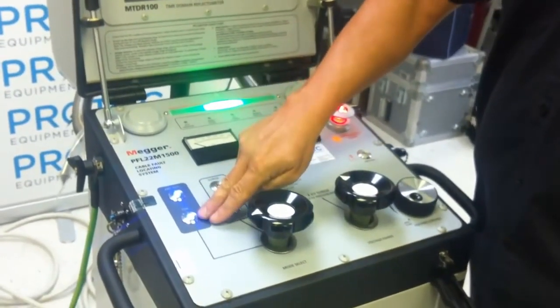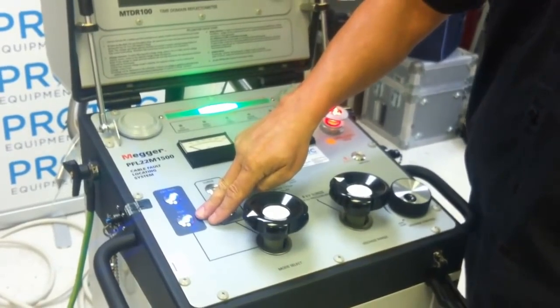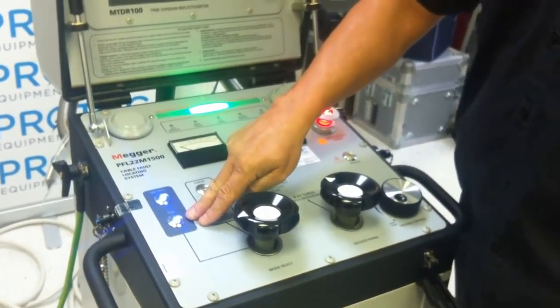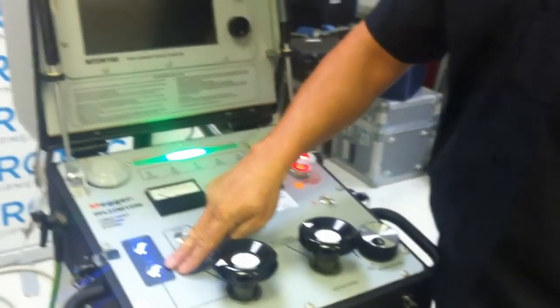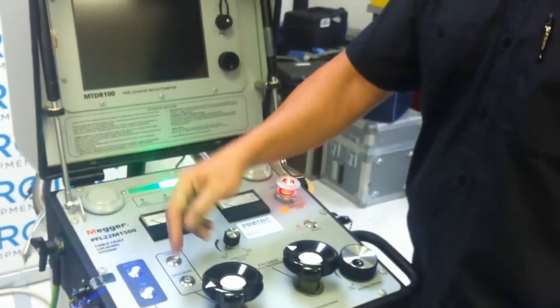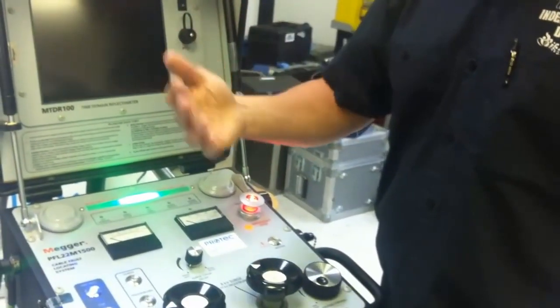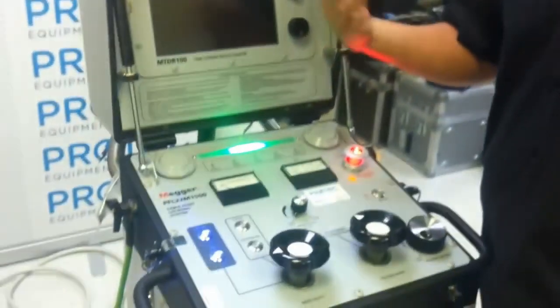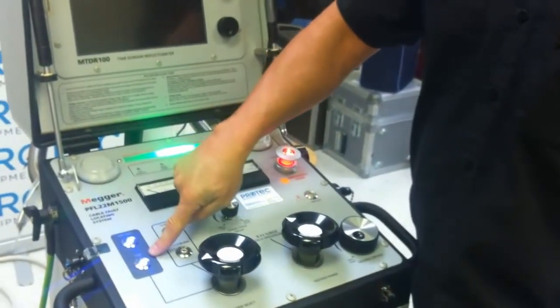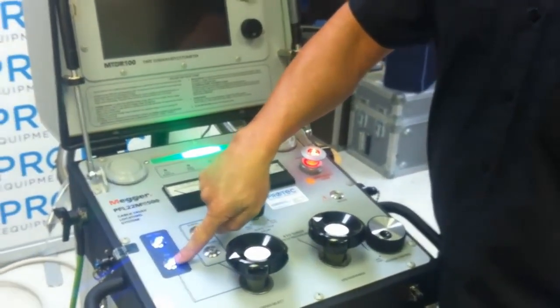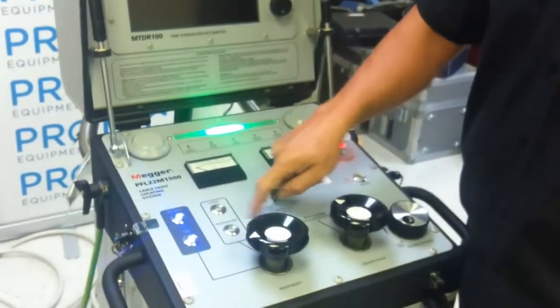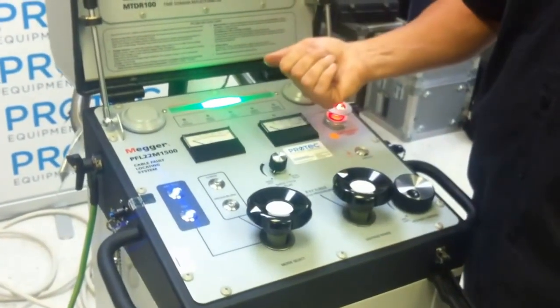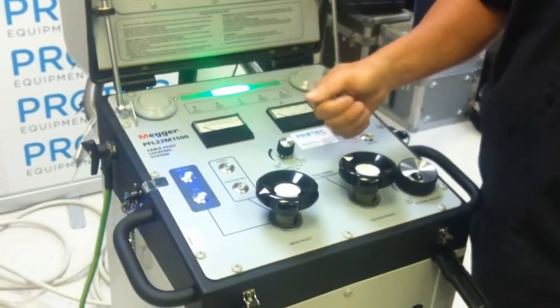So, purpose for the TDR mode, maybe it's a three-phase circuit, maybe it's an acceptance test, and all I want to do is document the three phases, capture the waveforms, take a look at the installation, the splices, etc. But I do not want to run high voltage, and I don't want the operator to be accidentally hit with high voltage. So mode select would be set to the arc reflection TDR mode. The appropriate button for TDR would be pushed, preventing high voltage from being brought into the circuit.